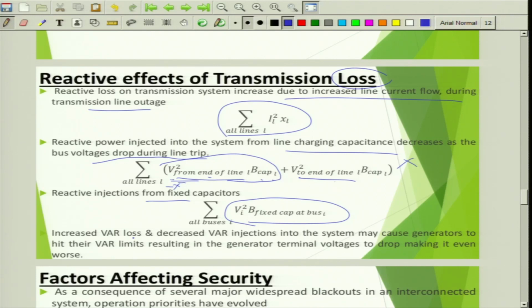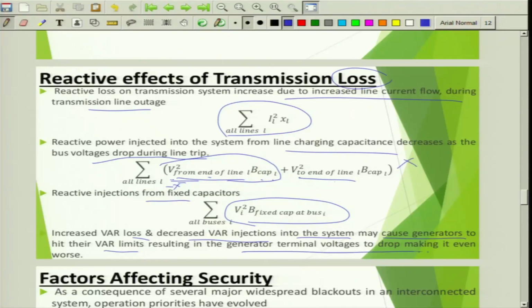So what happens? Increased var loss and decreased var injections into the system may cause generators to hit their var limits because the support devices, the shunt capacitance, are not present. Now generators will be overburdened because the load remains the same. Generators will be overloaded, and the remaining existing lines will also get overloaded, and because of which there is a further increase in line loss. This is a cascaded failure, and ultimately it will result in generator terminal voltage dropping, making it even worse. If the voltage drop increases, then there is further expectation from the generator to increase the reactive power.